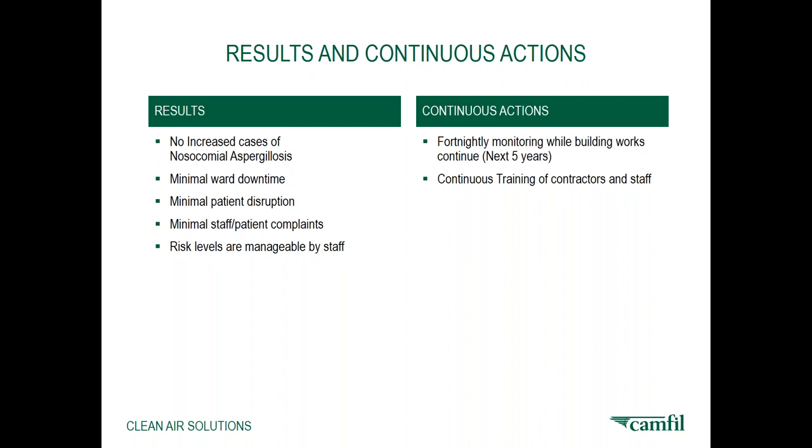We had to seal up all the egress points for dust particles to enter into the hospital buildings. And therefore, without mechanical ventilation systems, we had to introduce these air cleaners to provide air movement, fresh air cleaned and into the safe area. Over the continuous actions of the project, we continue to do fortnightly monitoring while building works are continued.